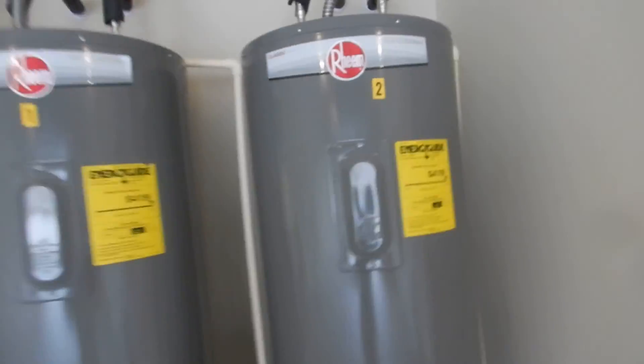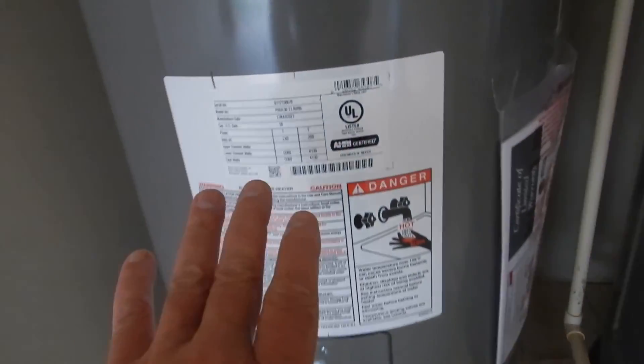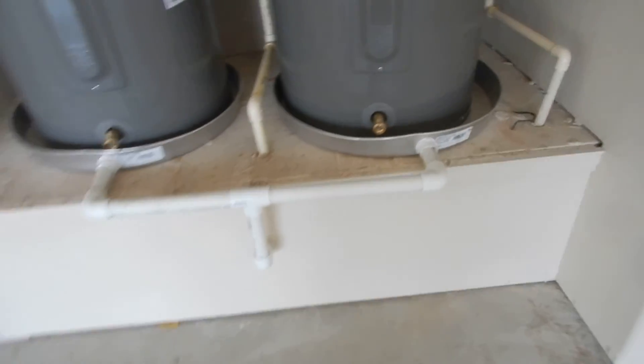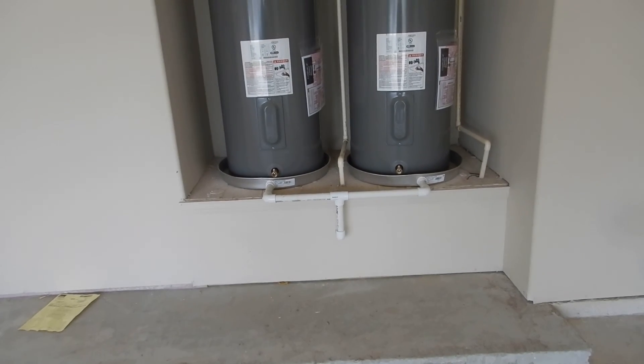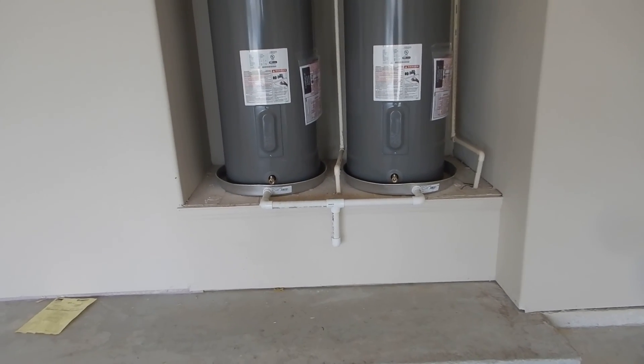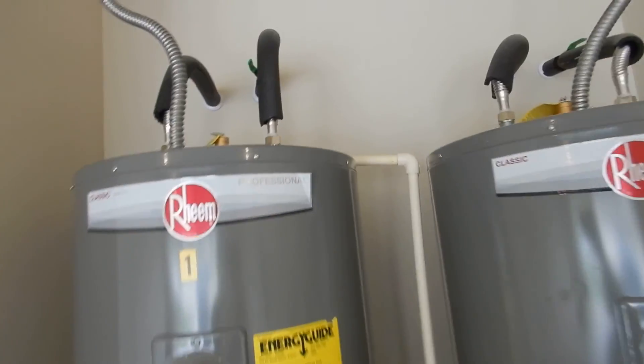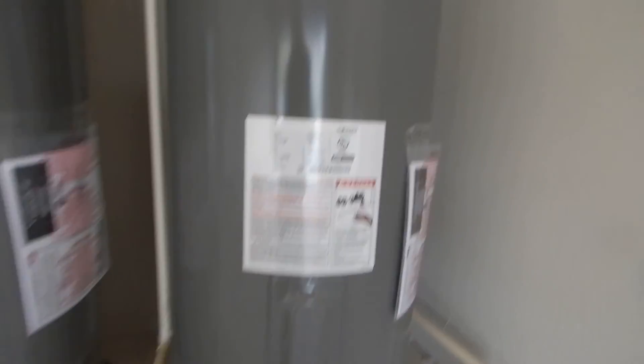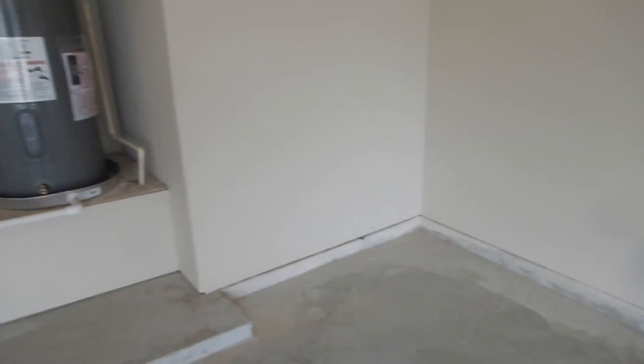Moving on — these are two 50-gallon water heaters. We've got still images of the data plates, and we already noted we have the care and use manuals. These are the safety pans and they're elevated. Really, the only things incorrect about these water heaters are: the insulation is a little short on the water supply lines, the temperature pressure relief valves are not insulated, and the piping discharges higher than six inches from the ground.